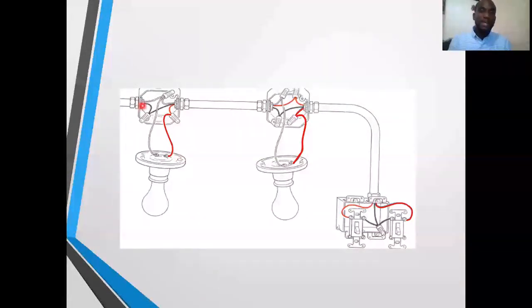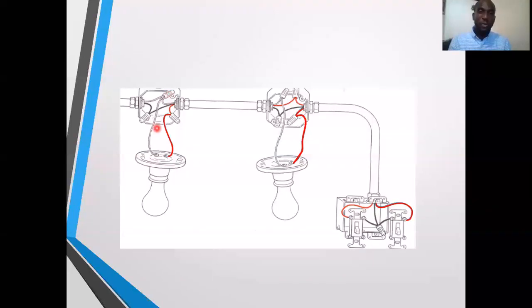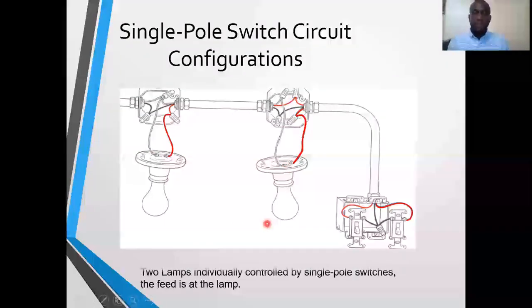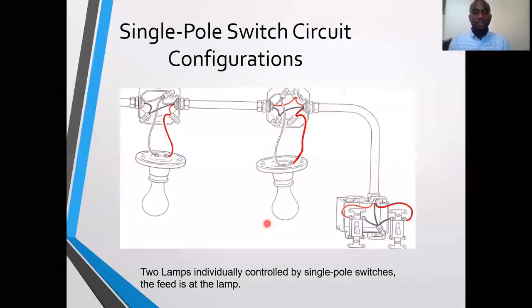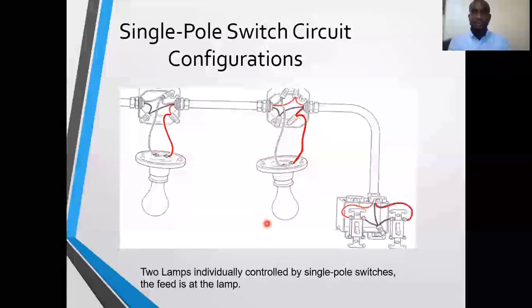From the source, we will splice the white or share the white, connect it to the silver terminal and then send it through to be connected to the next silver terminal on the opposite lamp. So there you have it. Two lamps individually controlled by single pole switches and the feed is at the lamp.